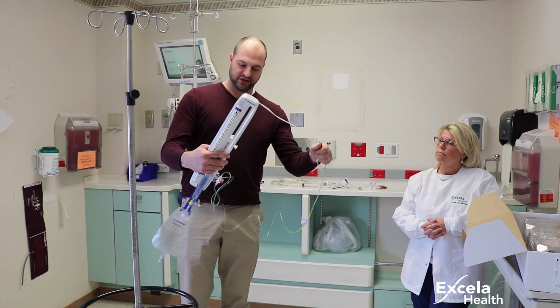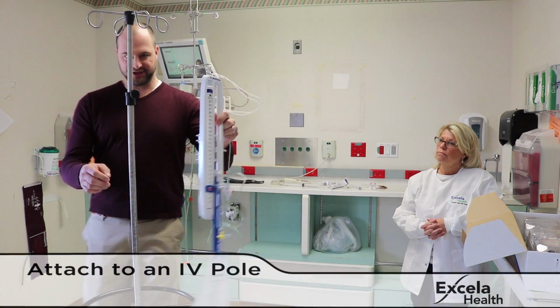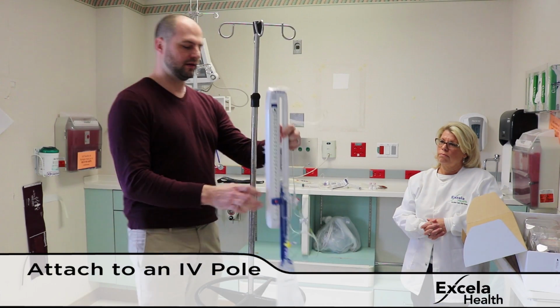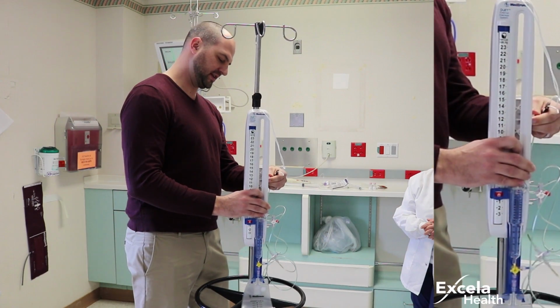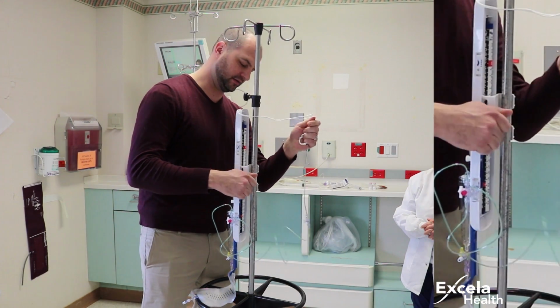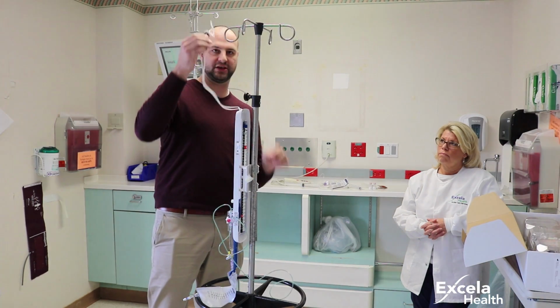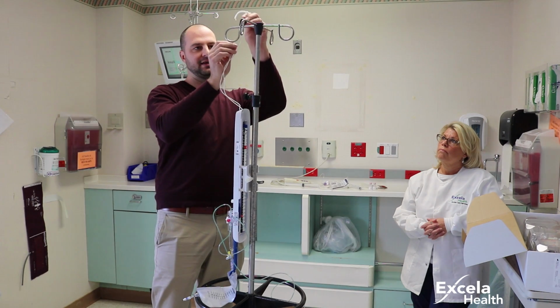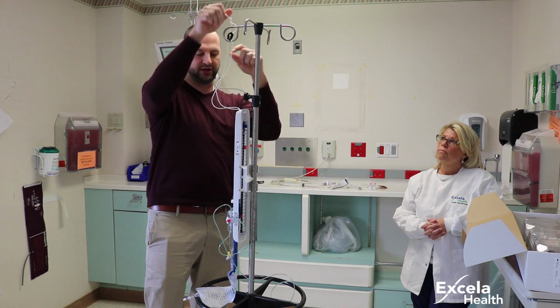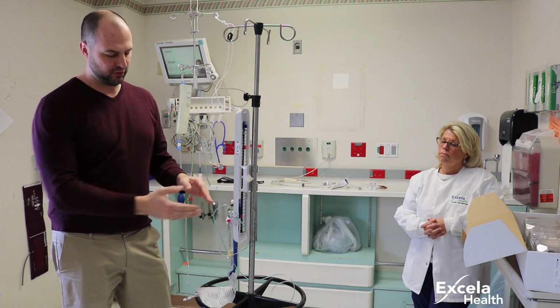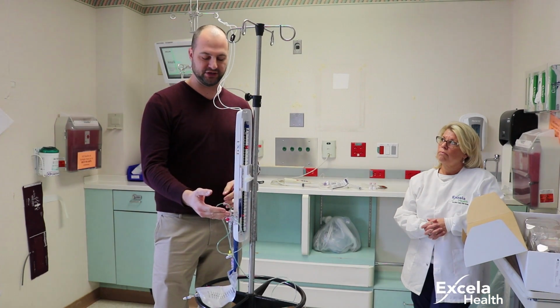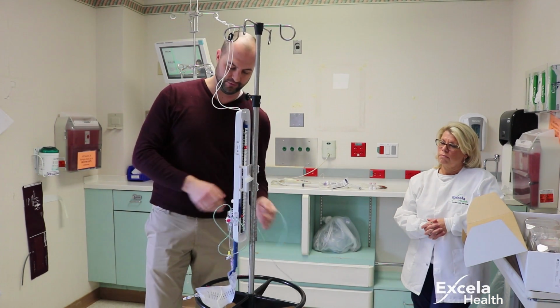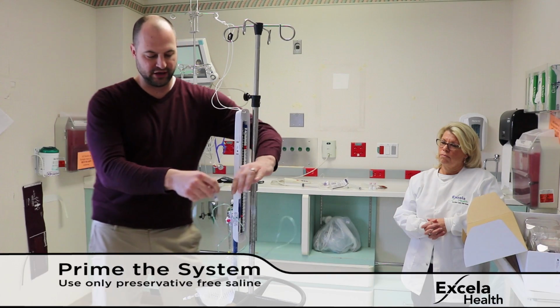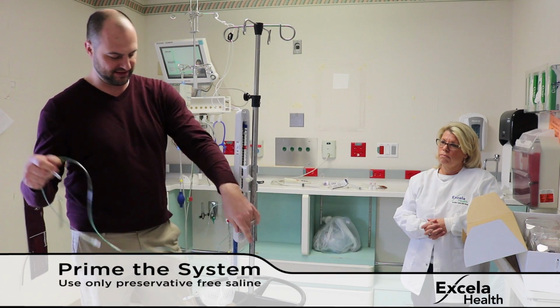Once we're connected to the actual system, we're going to go ahead and attach it to the IV pole. It's just a simple twist-on scale, twist onto the pole back here. For safety reasons, we're going to make sure that we have the tie on the IV pole, and you can adjust this to make it more taut. Once we get this level to the patient, wherever the patient is, the bed, that's where we're going to keep it level. Once everything's assembled, we're then going to go into the priming aspect of the system.